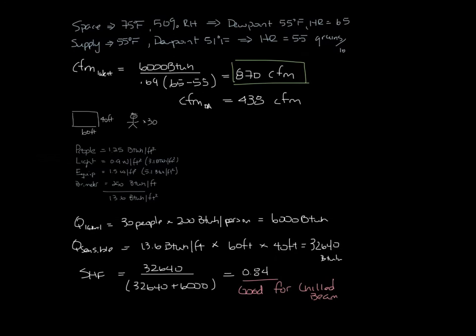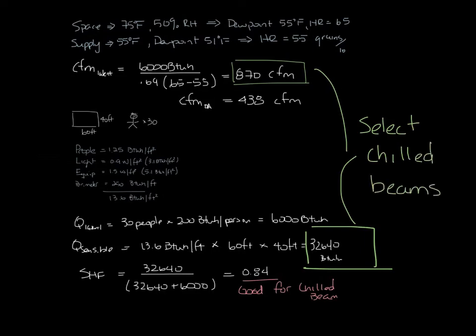Now look down here, you can see our sensible load is 32,640 BTU, and we just calculated our airflow at 870 CFM, and that's how we'll select our chilled beams.